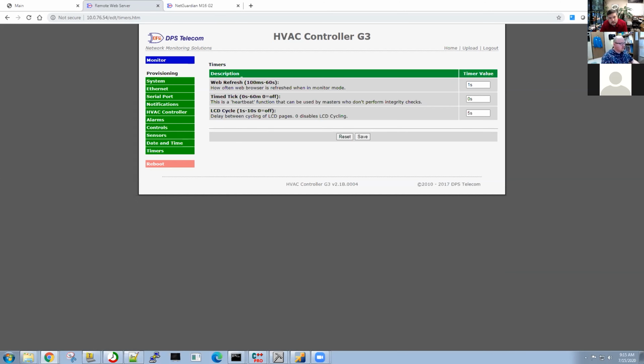Let's see, beyond that we've got timers. This one doesn't have a lot of timers. The web refresh is basically how often we're refreshing numbers inside of monitor mode. This timed tick is useful as an alarm. Sometimes a monitoring master station basically receives traps only and doesn't have any kind of poll process, in which case it's hard to tell if something's alive or dead unless something's going wrong with it. If everything's fine it's just not generating notifications, so it's typically used as a heartbeat kind of idea. LCD cycle is a delay on cycling the LCD panel on the front, so there's a number of different status windows it'll cycle through if we're not in any kind of configuration menu.